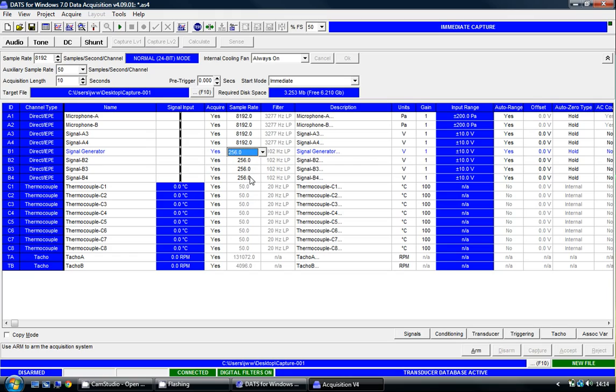As you can see, all four have now changed for Module B. When you change one, you change all. We can have different sample rates on different modules. So here we have three different modules and three different sample rates.